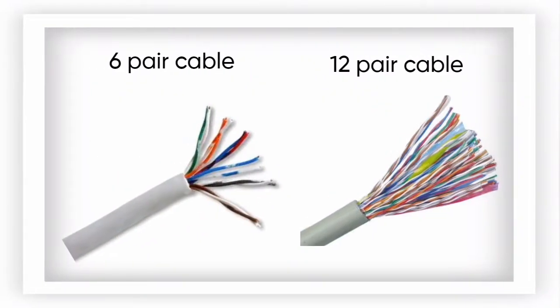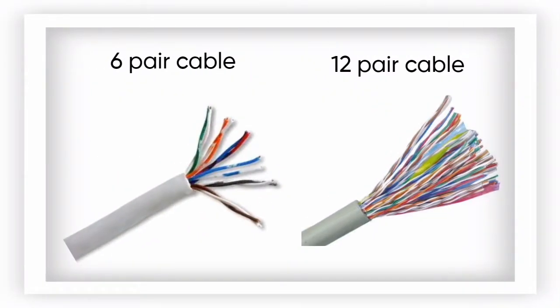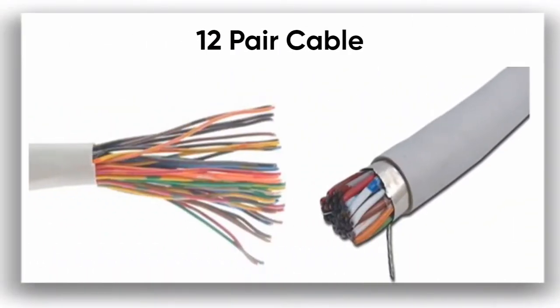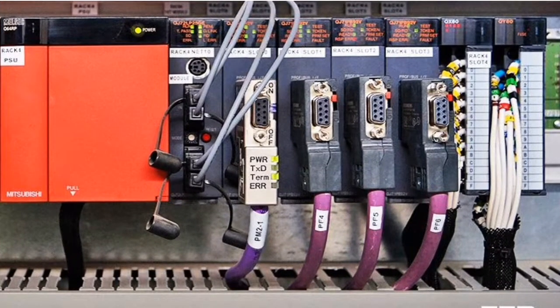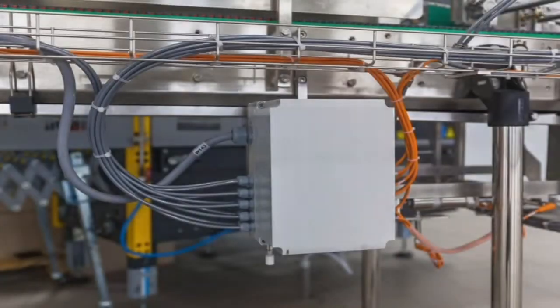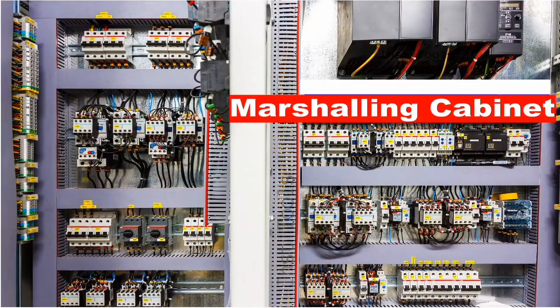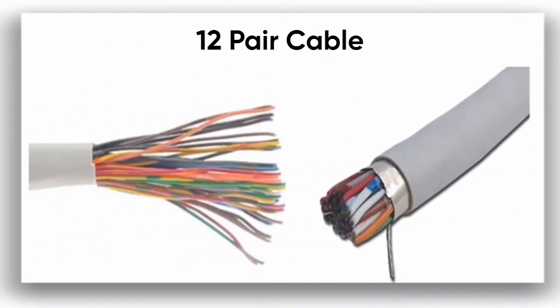So at least a six-pair or 12-pair cable is best suited for our requirement. We choose a 12-pair cable, which is nothing but a main cable or home run cable, as it interfaces the field junction box and the marshaling cabinet in the control room. So finally, one big main cable is required for our purpose.